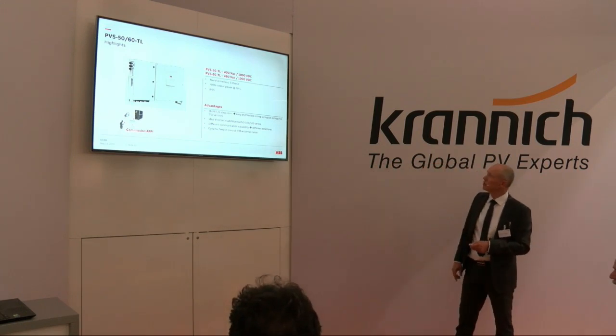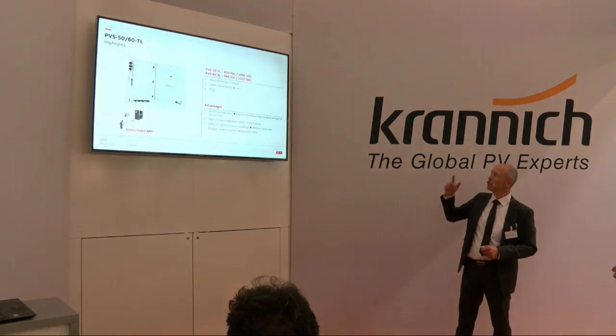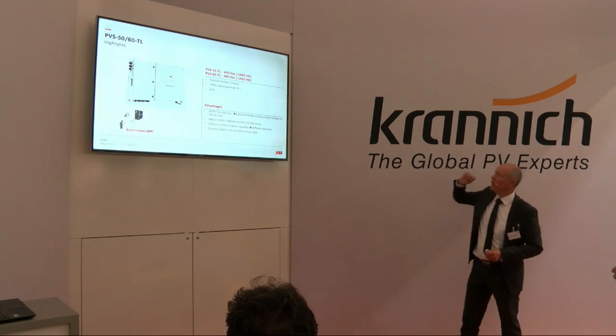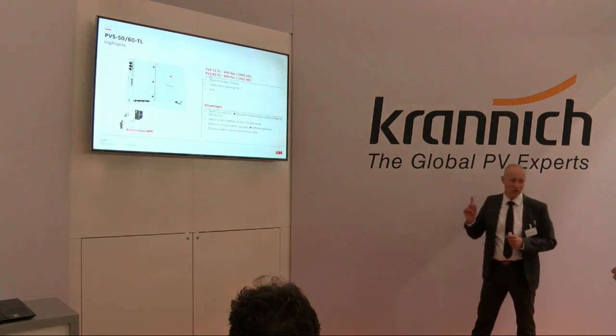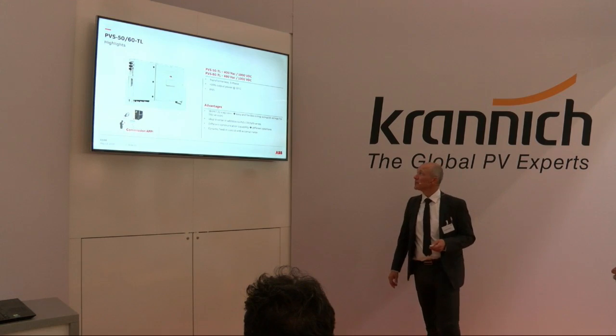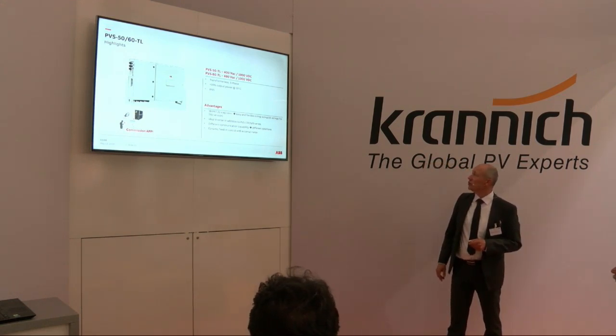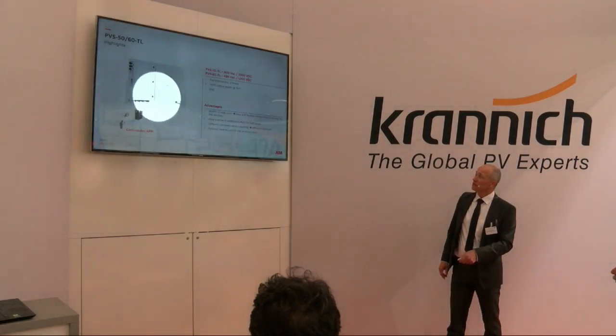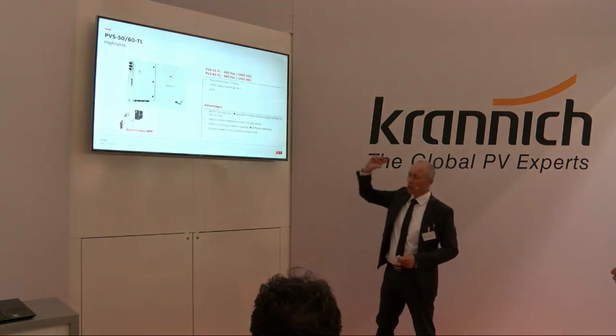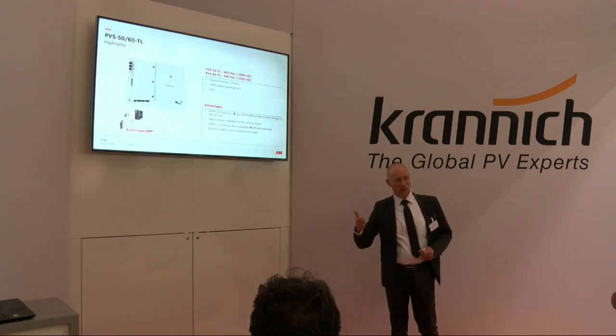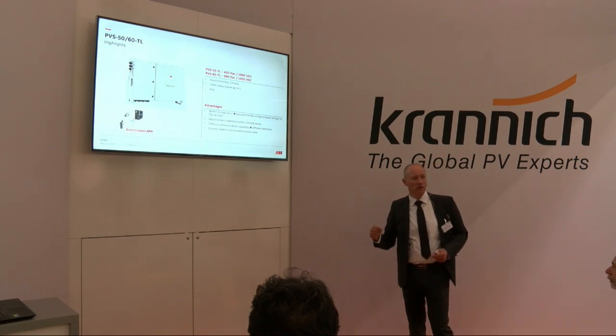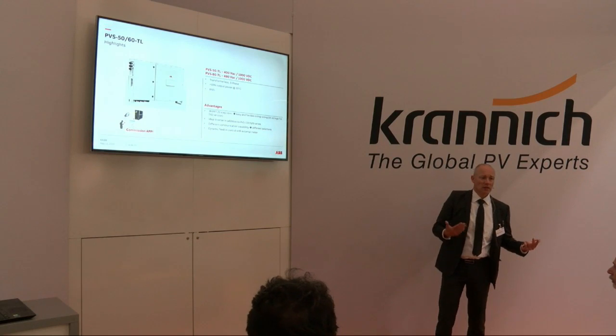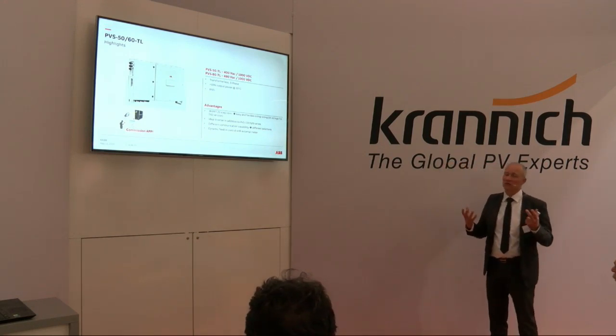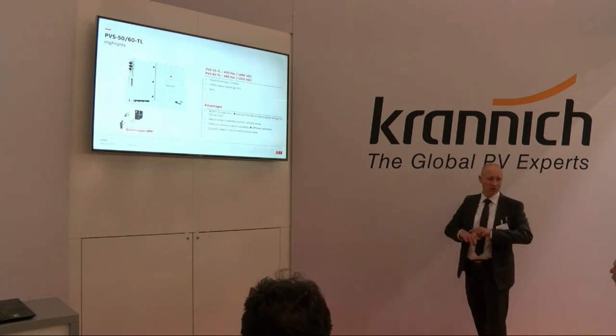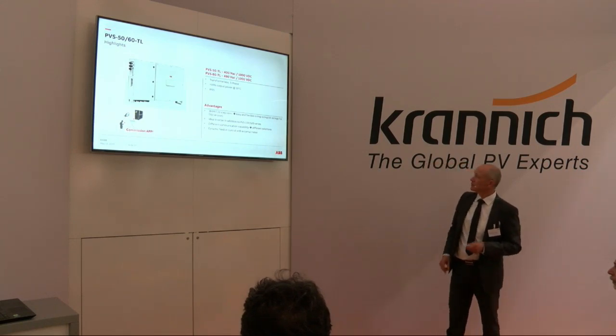However, we have two different topics. One is that with this inverter we have 10% more up to 30 degrees. So up to 30 degrees we have not 50, we have 55, and for the 60 we have 66. So 10% more power for these inverters. Another topic is that we can also do an S version. This inverter has 3 trackers, so we can combine all trackers together. We have only one MPPT then, and we go on terminals. In case of a retrofit of an old system, you can come with string boxes up to 50 kilowatts directly to the inverters without any reinstallation or new installation. And this is also very good.